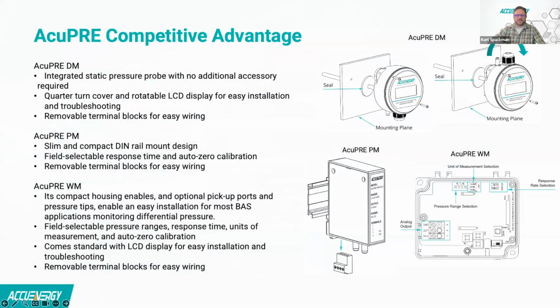A couple of installation features I want to highlight with this product. The AccuPre DM duct mount unit has an integrated pitot tip or pressure probe already directly mounted on the back of the enclosure that you do not need to install in the field. It has a quarter turn cover on the IP65 enclosure, and the LCD within the enclosure can be rotated. So if you need to put the wire access at the top of the enclosure, you can rotate that in the field if required. And then removable terminal blocks across all of our products simplify wiring on the unit.